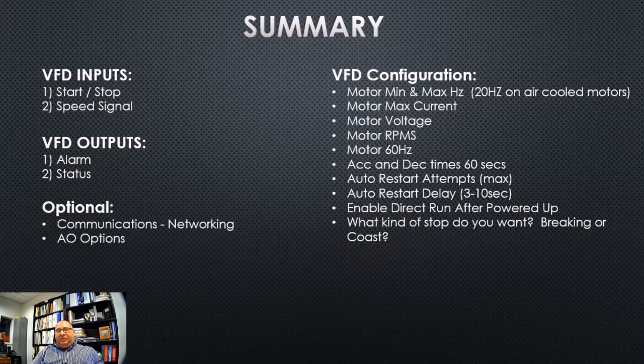What's going to happen is, if you leave the job site and you do not set that, you're going to get a callback, which means that every time you have a power failure, you're going to have to manually start it. We want to enable that for a direct run after power up. And one other thing you want to consider: do you want it to brake or to coast? This is the stopping capability of the fan. There are pros and cons, so usually we say coast to stop so we don't damage the equipment. But if you need a quick emergency brake, such as for a smoke alarm, you could have that option as well.